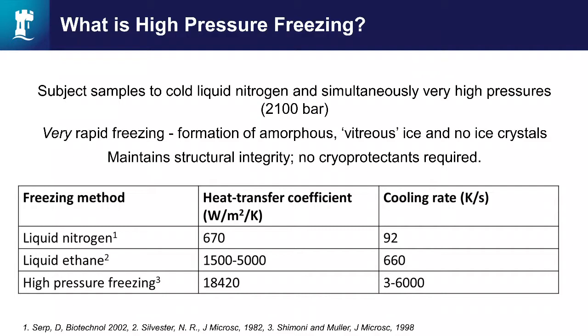I've got a table here that compares different freezing methods. So we can plunge into liquid nitrogen and that is a relatively slow cooling rate because it's a relatively small heat transfer coefficient for liquid nitrogen. You do get a vast improvement if you move to freezing your samples in liquid ethane, but high pressure freezing, you can see there's an order of magnitude improvement in the quality and the rate of freezing because you get such a rapid cooling rate.